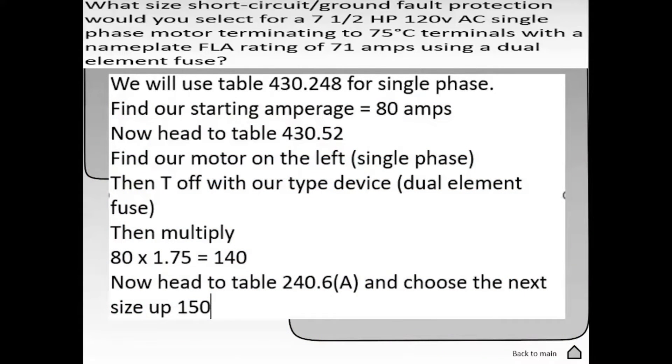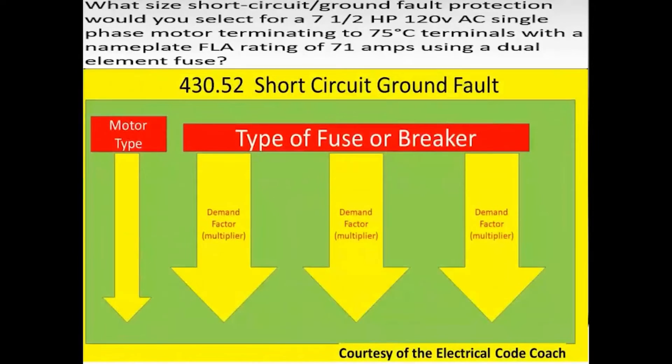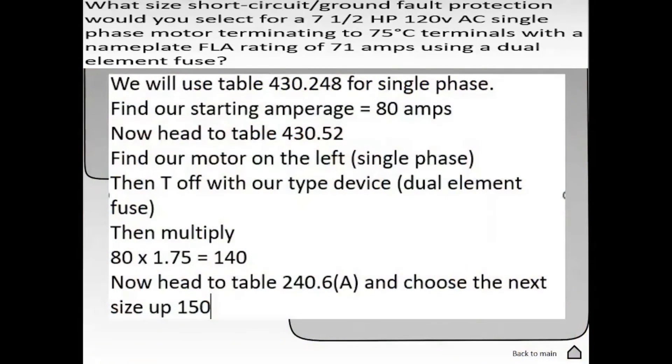Now we're going to head to table 430.52 and we're going to find our multiplier. We start over here on the left hand side and find our type of motor which is single phase, then we come across here until we find our type of device which is a dual element fuse. We find that the multiplier is 175%. Then all we have to do is do the math.